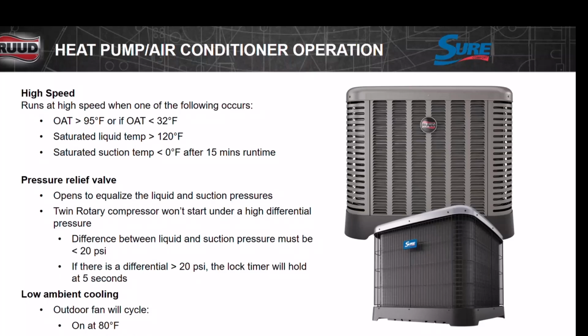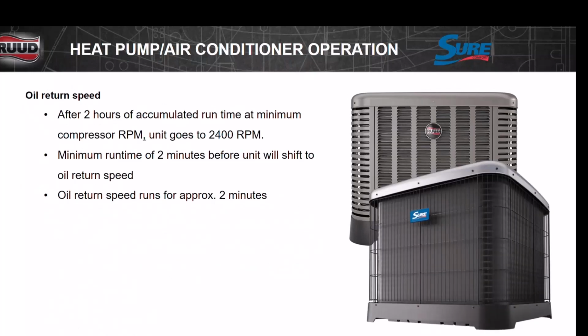Outdoor fan cycle, it's on at 80 degrees and off at 64 or 40 psi, so we're cycling that fan outside. This is one thing I always tell you, remind your customers, let them know this is going to happen. Because you're going to see them out there at the pool or on the barbecue or whatever they're doing outside. They're going to be outside, and all of a sudden this unit's going to ramp up to 2,400 RPMs from running it slow for 2 hours, and they're going to go, wait a minute. Then it went back to low, and they think it's broke.